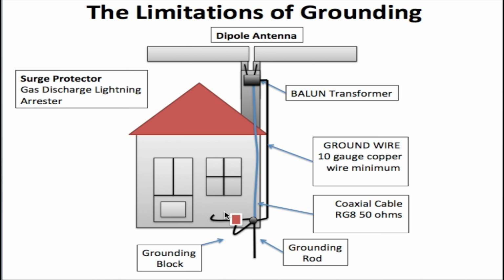Now this surge protector being in this particular location serves two purposes. It prevents surge currents from lightning storms from getting to your equipment. It also prevents surge currents that are coming from the ground from getting to your equipment. You see, if there's a lightning strike further away, that current goes to ground. Just like we dissipate the current here to ground, it is also dissipated to ground anywhere that it strikes. And that current goes to ground and it would get to your grounding rod, and it would go up your grounding rod, and it would go into your home in the same way. So this surge protector serves two purposes: it protects your equipment from surge currents resulting from direct antenna hits or from ground currents.